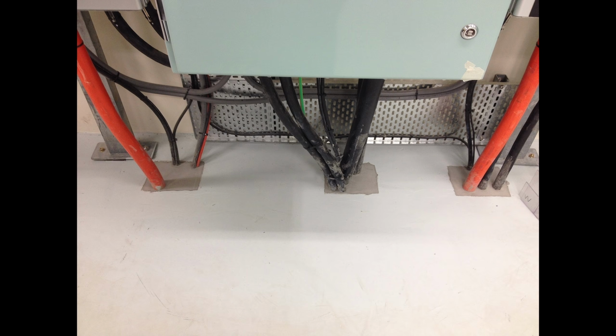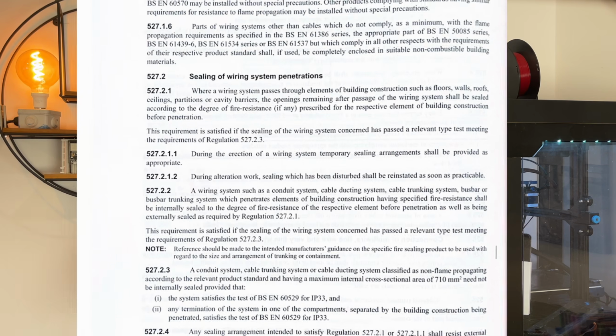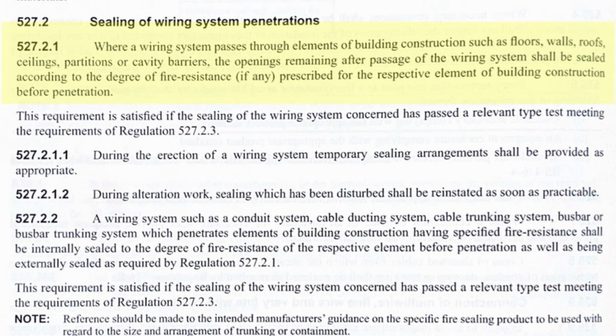Talking of fire, we get into protecting fires from spreading through the holes which electrical cables pass through. The old school way was to leave these holes as they were and just poke the cable through, but regulations such as 527.2.1 require a degree of fire resistance, and there's quite a few different methods for ensuring this. Basically, we want to reinstate the hole that we've put in.